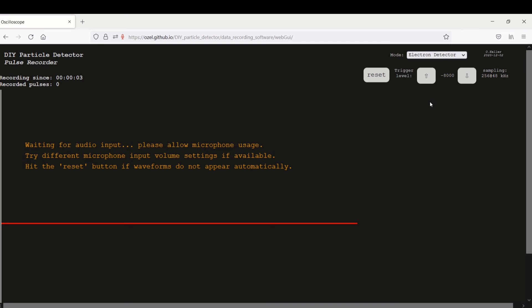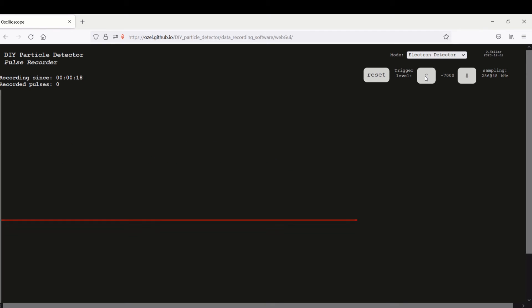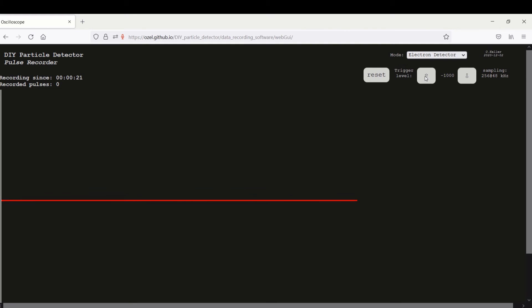And now you can select, first you select if you have the electron detector version or the alpha spectrometer version. We have the electron detector version and here you can raise or lower the trigger level.